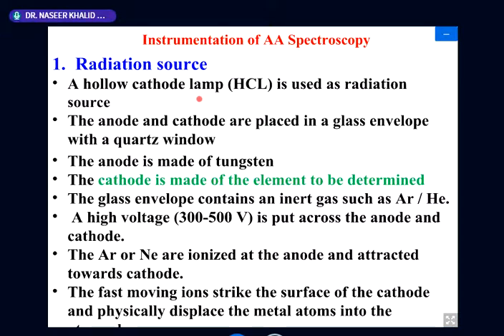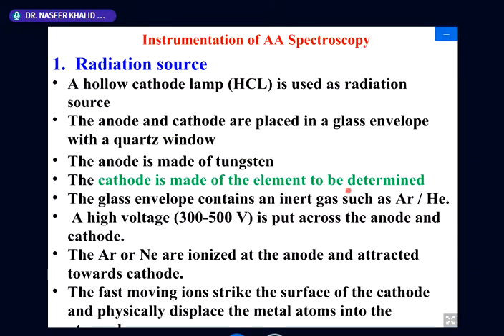In the hollow cathode lamp, there is a bulb with two electrodes: an anode and a cathode. Both electrodes are placed inside glass sealed with a transparent quartz window. The anode is made of tungsten, and the cathode is made of the element to be determined. This is the speciality of the hollow cathode lamp.